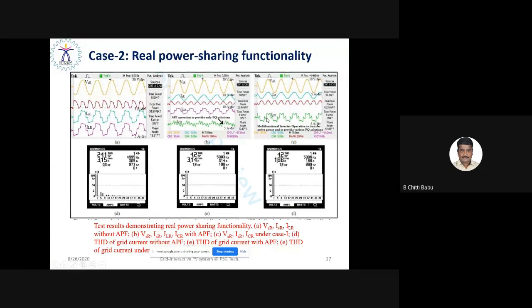What do you mean by real-time power sharing? For example, if the PV is generating 1 kilowatt of power and the grid requirement is 1 kilowatt, obviously the grid power and the source power remain the same, so there is no need for additional real power sharing. But when the load power increases from 1 kilowatt to 1.5 kilowatts, the PV power remains 1 kilowatt, and the remaining 0.5 kilowatts will be supplied by the voltage source inverter from the PV. This is what is called real power sharing functionality. You can see that it also contributes real power sharing capability, and moreover, it also maintains the power quality.